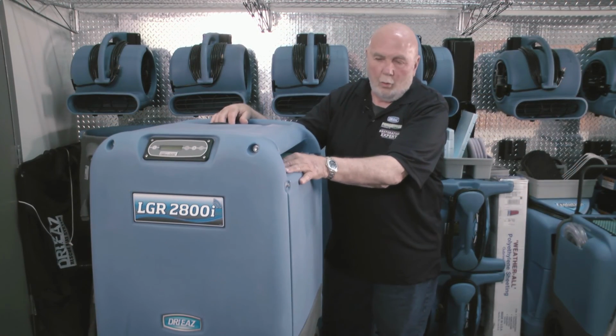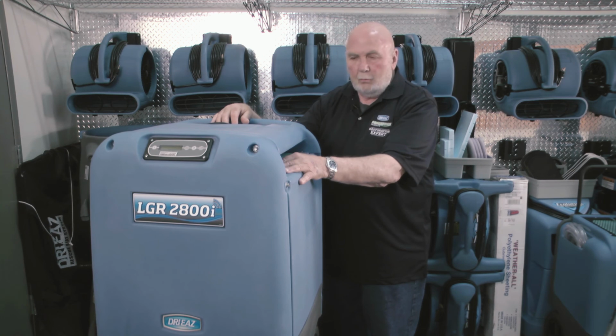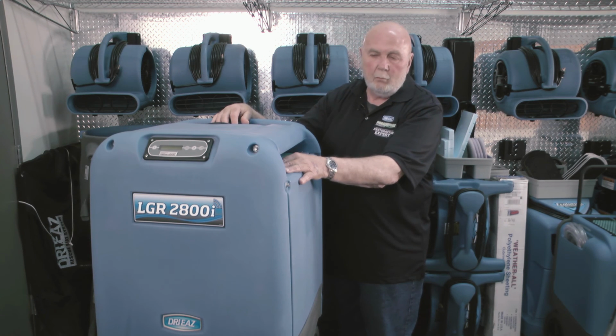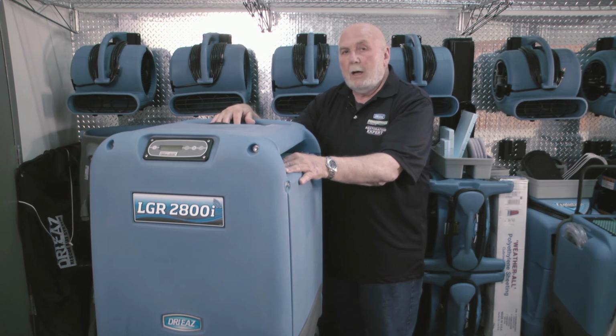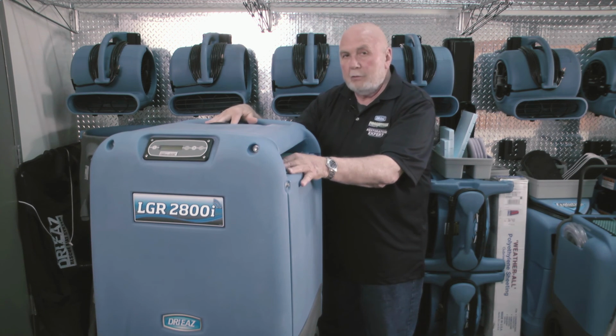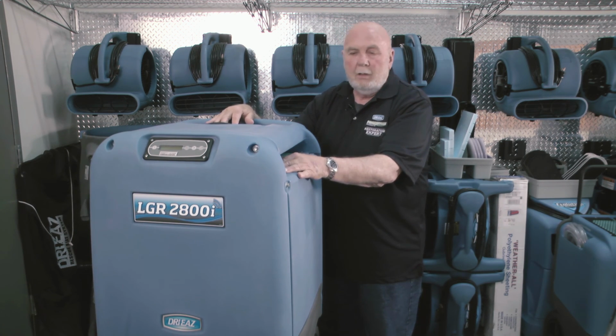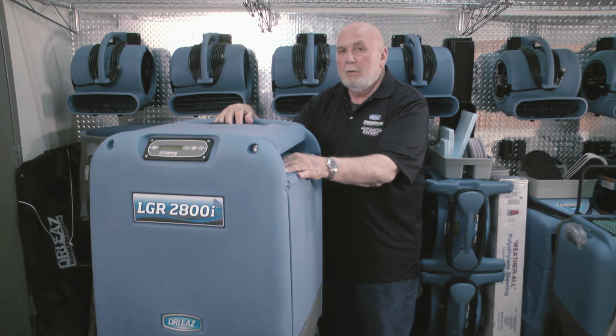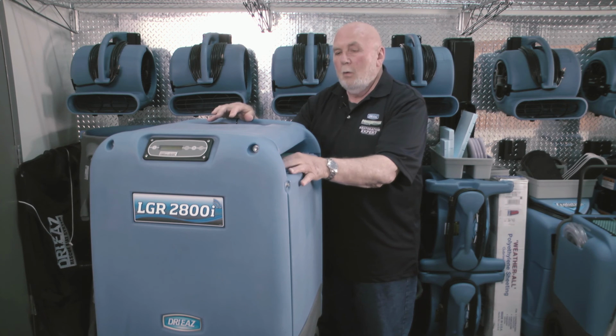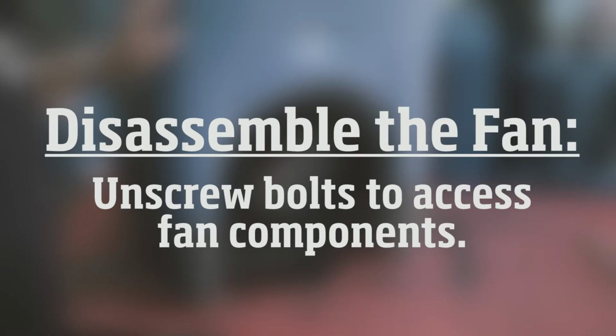Today we're going to go over the disassembly of the unit. We're going to remove the fan, the pump, and the high voltage panel down below. We're going to remove the cover, the heat exchanger, and generally just disassemble it, letting you know what you need to clean, what you need to look at, and verify when you have issues.